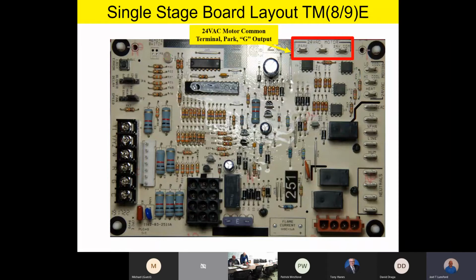Then you're going to notice there's another terminal that says G. Now that G terminal is going to go down, and you're going to select a fan speed appropriate to like a continuous airflow. So in other words, if you just want to have continuous airflow going, a nice low airflow going across that air filter all the time, typically you're going to find that G is going to be selected on low speed on the fan. In addition, right next to the G terminal, you're going to find a 24 volt C common. That's a 24 volt input to the motor itself, but it's the common. So those terminals right there will be going down to the motor on the 24 volt terminals. And again, G will be typically selected on your lowest speed, and then 24 volt common will be to the common 24 volt common terminal on the motor itself.